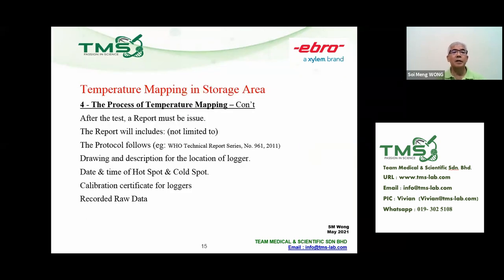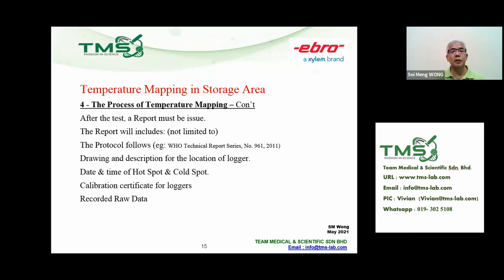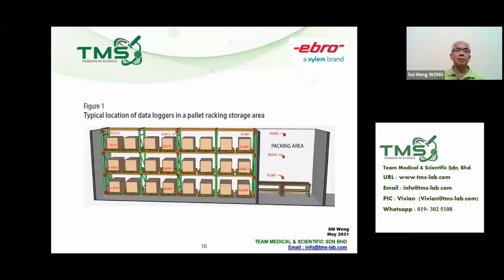After the test, a report must be issued. This report will include, but is not limited to: the protocol followed — for example referencing the WHO Technical Report Series — a drawing and description of logger locations, the date and time of hot spot and cold spot occurrences, the calibration certificates for the loggers, and the recorded raw data. An example of logger location naming is shown for a pallet racking storage area, where all loggers are named with a description of where each is placed.